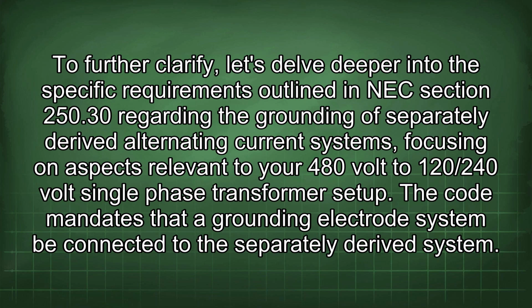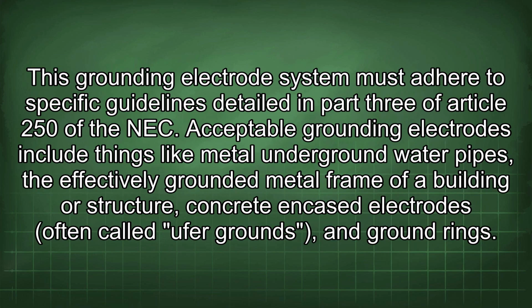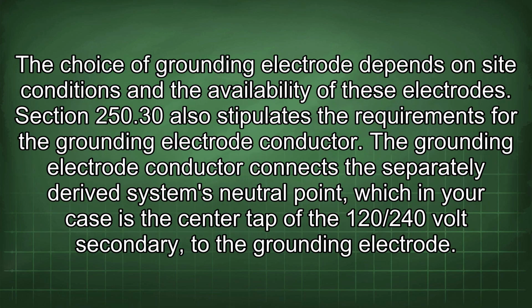To further clarify, let's delve deeper into the specific requirements outlined in NEC section 250.30 regarding the grounding of separately derived alternating current systems, focusing on aspects relevant to your 480 volt to 120/240 volt single-phase transformer setup. The code mandates that a grounding electrode system be connected to the separately derived system. This grounding electrode system must adhere to specific guidelines detailed in Part 3 of Article 250 of the NEC. Acceptable grounding electrodes include things like metal underground water pipes, the effectively grounded metal frame of a building or structure, concrete encased electrodes often called Ufer grounds, and ground rings. The choice of grounding electrode depends on site conditions and the availability of these electrodes.